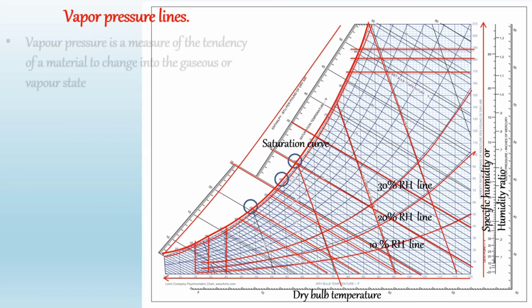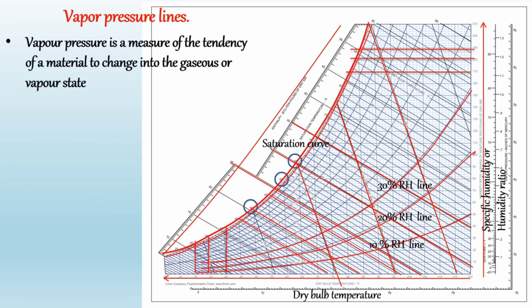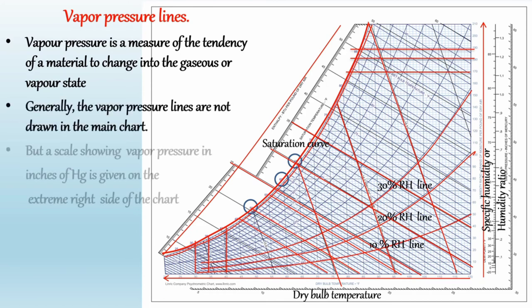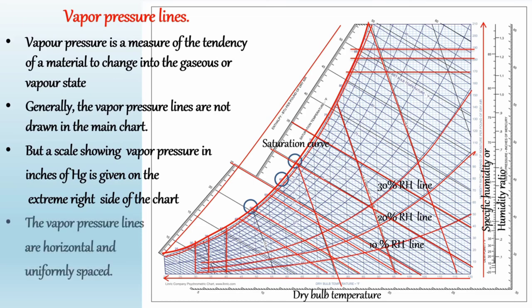The next line is the vapor pressure line. Vapor pressure is a measure of the tendency of a material to change into the gaseous or vapor state. In the psychrometric chart, generally the vapor pressure lines are not drawn, but a scale showing vapor pressure in millimeters of mercury is given on the extreme left side of the chart. The vapor pressure lines are horizontal and uniformly spaced.